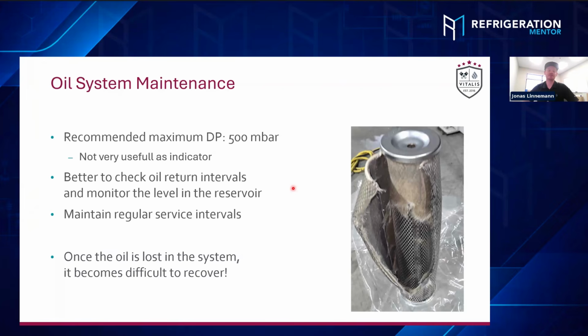Nevertheless, just maintaining the regular maintenance intervals, especially after the initial startup, like maybe the next day, maybe the next week, is definitely the right time to replace the first cartridge, because at the beginning, there's little fine debris out of the whole field piping and everywhere. It all gets stuck in that cartridge at some point. And to replace that right after the commissioning is very important. Then maybe a month later, and then in typical intervals, right? And then you don't run into any risk of breaking a cartridge. And that's important.